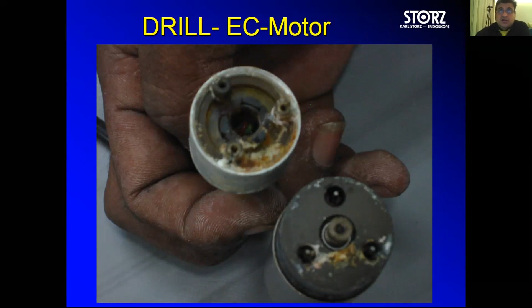Now, why is it important to have a medical grade oil? The oils have different viscosity. When I was studying engineering, we were taught, oh, this is viscosity 40, this is 60, this is 80. So for the special medical instrument, a special type of viscosity is defined. It is not that I use the oil in the hair, so okay, it's also a lubricant, so let's use it. So proper viscosity should be there because that defines the heat dissipation capacity of the equipment.